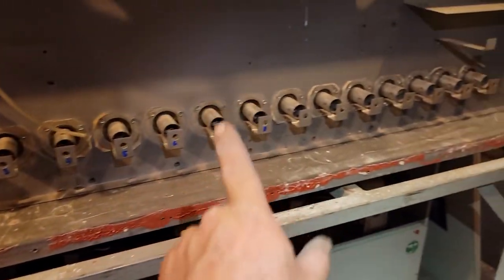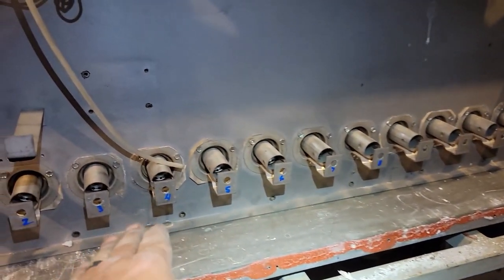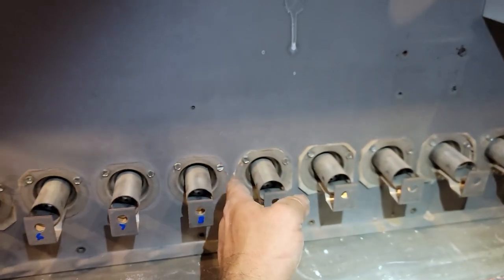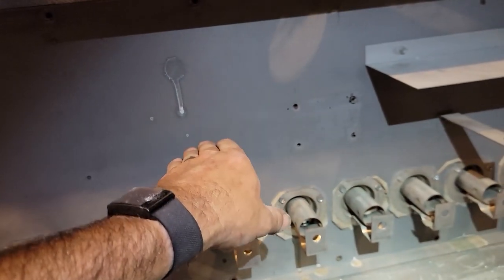Obviously the factory said remove the burners. The biggest thing I would say you have to do if you're going to do it like I just did it, is make sure you keep it lifted up, pulling back at the top, pushing at the bottom, keeping it level. Make sure you don't hit that divider, don't skid it across that refractory plate.